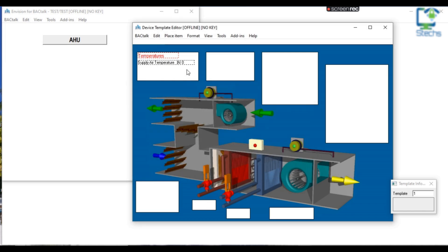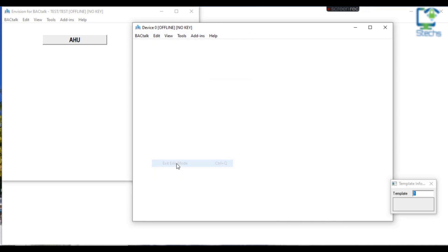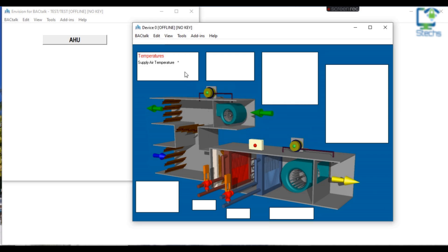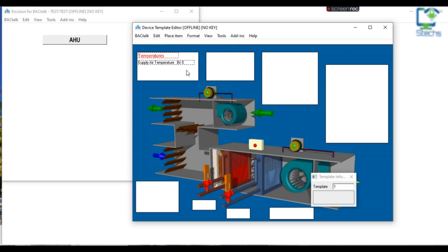After that, click on Edit from the menu bar, then click Save and exit edit mode. Since there is no controller connected and no license used, we cannot see the value of the temperature. So I am changing the type from AI to AV. Then save and exit the device template window — now you can see the value 0 degrees Celsius.